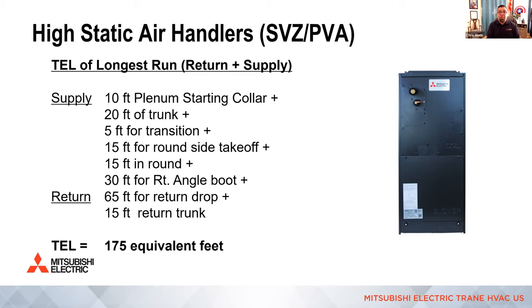Now, as we come down towards the end, you'll see there's a side takeoff. If it's a round side takeoff off of the trunk, sorry, then we account for 15 feet. Remember I was saying anything off the top, and this happens a lot in the basement because people like to hide those takeoffs up inside bays. If they come off the top of the trunk, that's a 40 or 50 foot fitting compared to coming off the side with a 15 foot fitting, all right? So big difference. Now, what you want to do is keep the lowest equivalent length values for the ones that are furthest away.